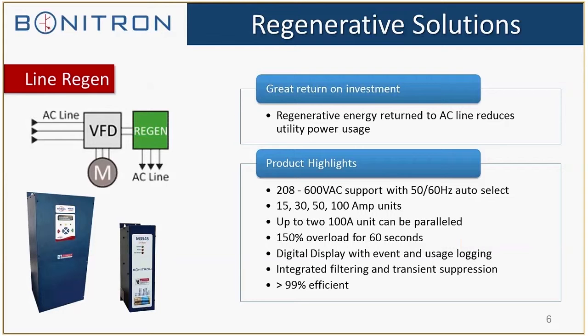Moving on to our line regeneration models. We have two separate part numbers. Our smaller units are the M3545 units, which are 15 amp, 14 horsepower units. All Bonitron regen modules are rated at 100 percent duty cycle, meaning the capabilities listed — whether 15 amps, 30 amps, 50 amps, or 100 amps — it can do that all day long, 100 percent of the time.